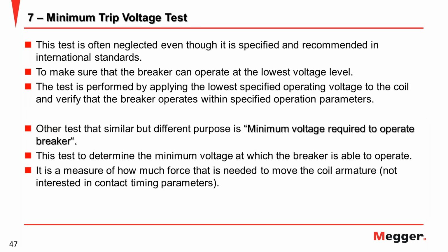Minimum trip voltage is also important. This is considered as additional testing. With this test, we want to define how low the voltage can be to still operate the breaker, because as you know, the voltage of the coil has a relationship with the breaker timing operation. If you have a lower voltage, the breaker operation time will be longer than with nominal voltage.